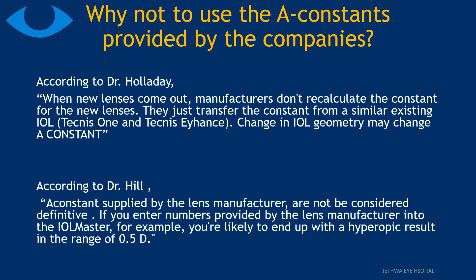According to Holladay, when new lenses come out, manufacturers don't recalculate the constant for new lenses — they just transfer the constant from a similar existing IOL. For example, Tecnis One and Tecnis Eyhance have the same A-Constant. A change in IOL geometry may change the A-Constant. Dr. Hill says that A-Constants supplied by lens manufacturers are not considered definitive; if you enter numbers provided by the manufacturer into the IOLMaster, for example, you are likely to end up with hyperopic results in the range of half a diopter.